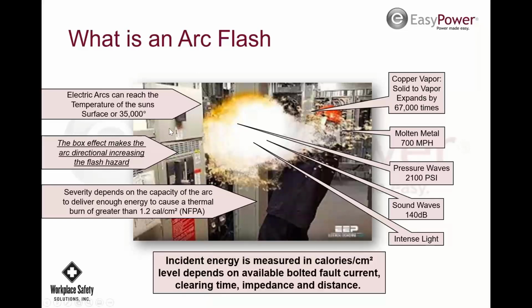So it's measured in calories per square centimeter. The level depends on several things. First off, what is the bolted fault current? The bolted fault current is everything that's available from the system, and it may be up to 200,000 amps on a 480 volt system. So if you have 200,000 amps, that's a lot of available fault current, and it's going to contribute to a large scale arc flash event.